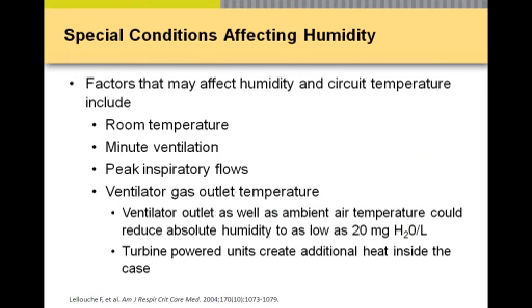If you look at conditions affecting the humidity, we all know temperature in the room, higher minute volumes, varied peak flows, and so on. But if you look at Lellouche's study in 2004, some ventilators that have higher temperatures at the outlet will actually affect the humidifier's ability to adequately condition the gas. So I'm going to tell you in those situations, you need to be observant.